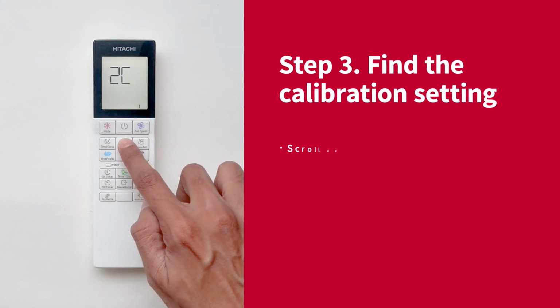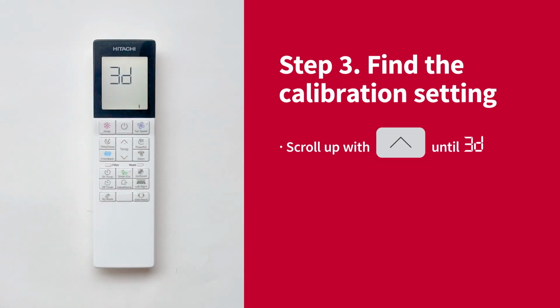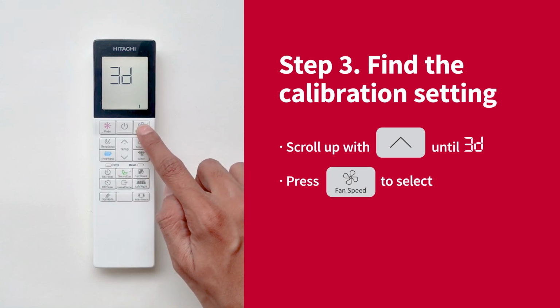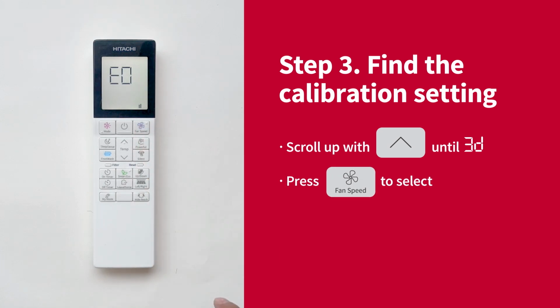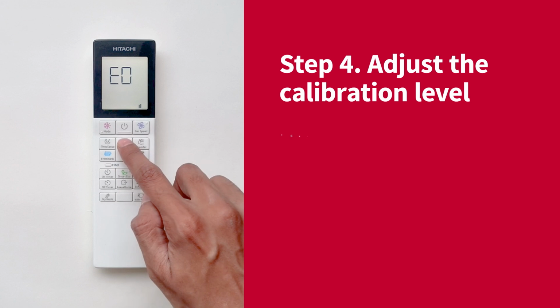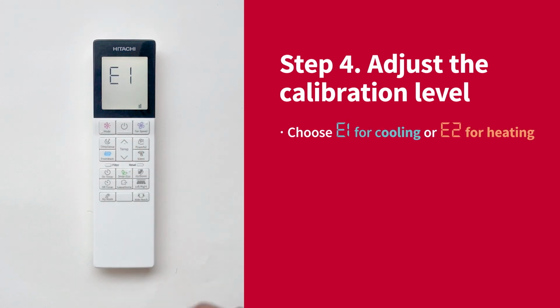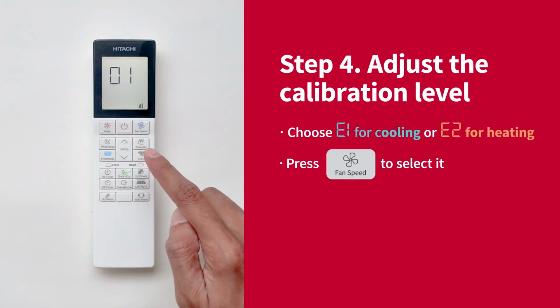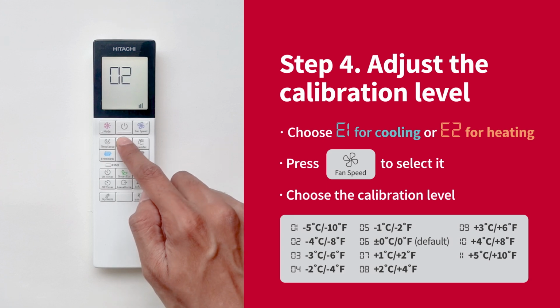Step 3. Scroll up with the arrow until you reach the 3D menu, referring to cycle operation settings. Press fan speed to select it. Step 4. Now choose E1 to calibrate the cooling set point, or E2 to calibrate the heating set point. Select the calibration level you wish to apply.